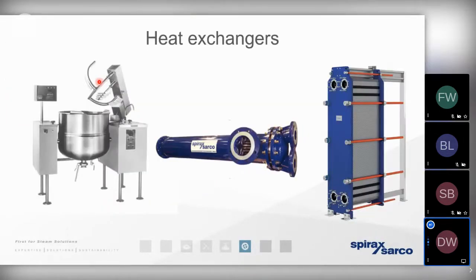So as we've already mentioned earlier, steam gives up its latent heat energy by condensing, by changing state from a gas to a liquid. So above you can see what we refer to as a typical closed loop system, a heat exchanger. That's when steam goes onto the heat exchanger itself, and that liquid condensate that's full of sensible heat that we cannot use has got to be drained away.